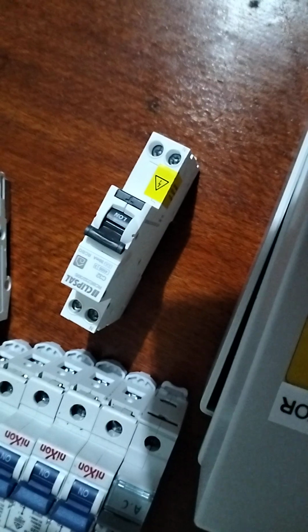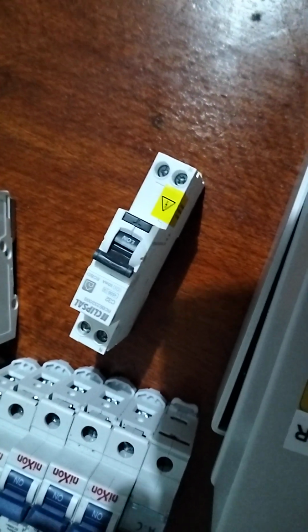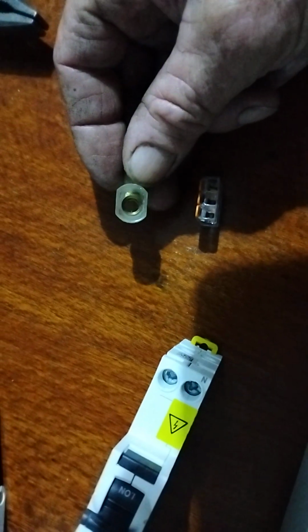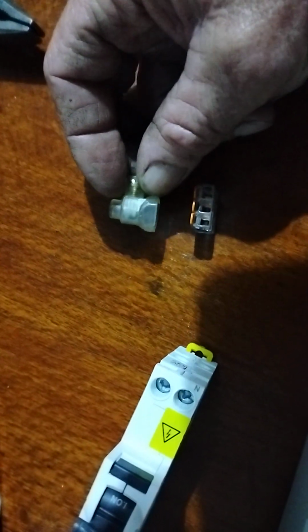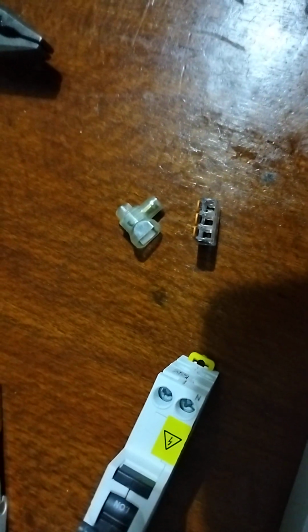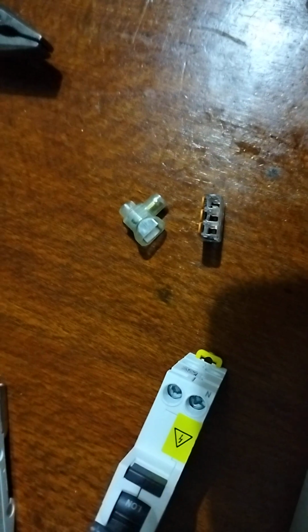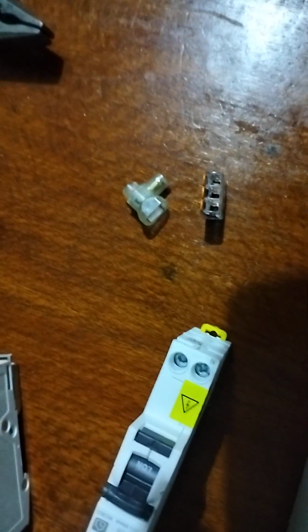Now, we hear a lot about these, I don't use these Wago connectors much, these things here. If I have to do a connection in floating wires, in junction boxes, if I'm not using a terminal strip, I'll use something like this. Your Wago terminals are much smaller, but you have one wire in each of those terminals. But this one here you can easily put 4 conductors of, say, 2.5 mil in there. I think they'll cap off a 16 mil by itself if you just want to keep it safe while you're disconnecting or something.